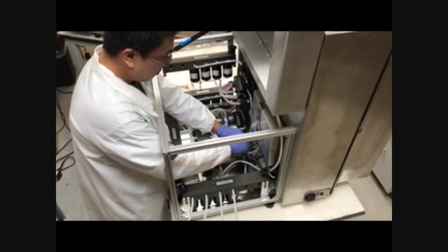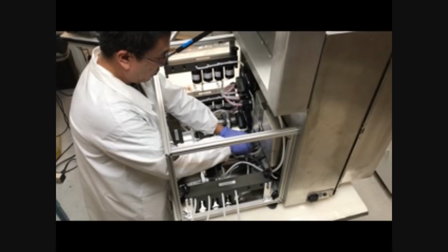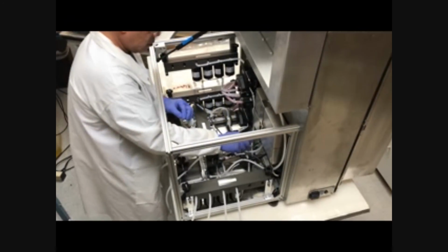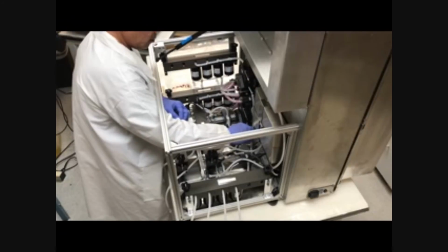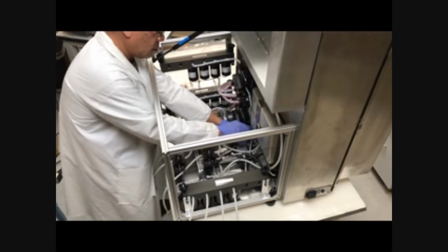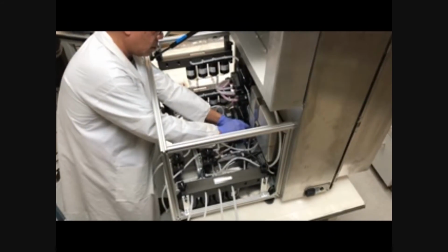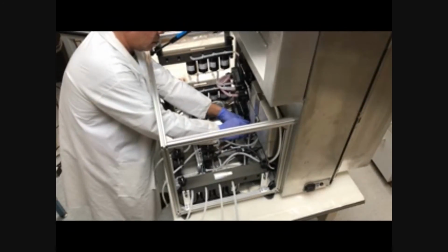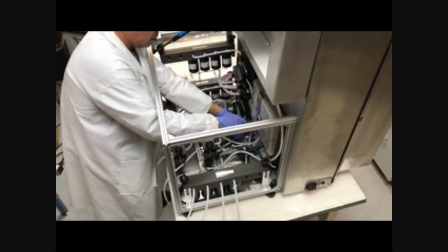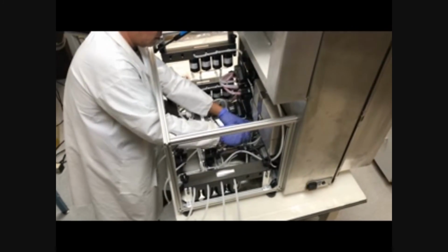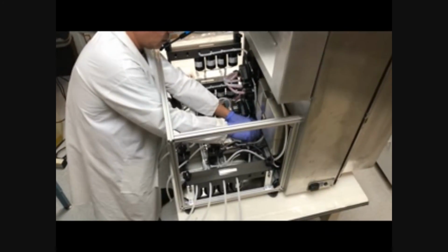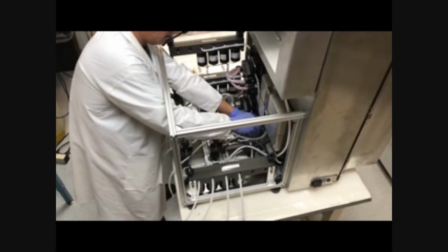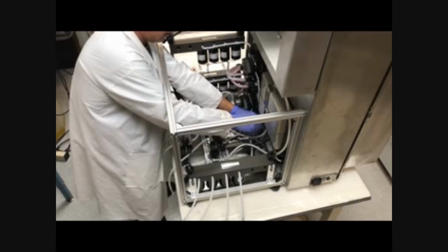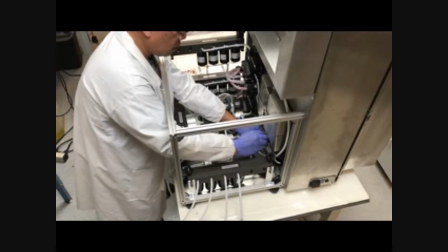And you can lightly tighten those with a screwdriver, which is what he's doing right now, so that they remain in position and don't move out, because you want the flow accuracy on these flow meters. It is astounding. It's about 0.1%. And it can go down to very low levels in terms of flow rate, so the flow range is excellent.